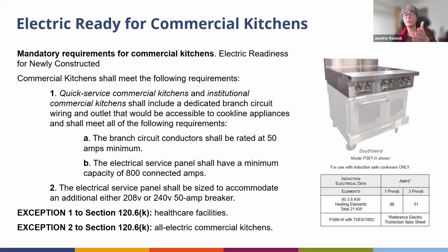So for example, this Southbend induction unit wouldn't be unexpected to see in a commercial kitchen, but if you do the 3-phase, you need 51 amps, 1-phase 88 amps. So that's why your branch circuit conductor should be rated at 50 amps minimum.